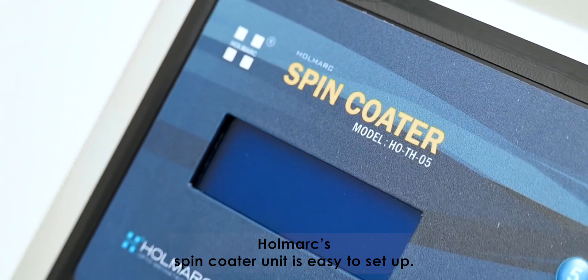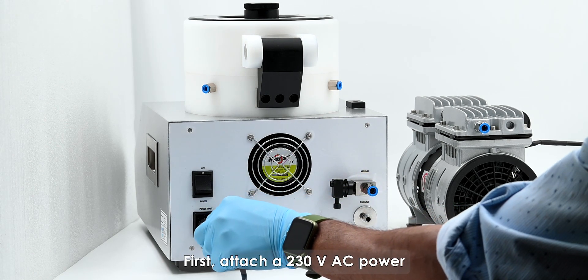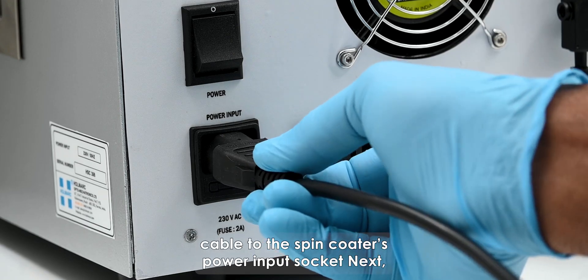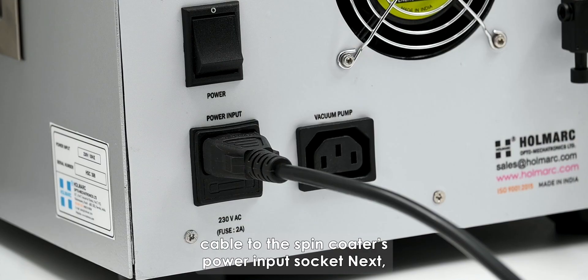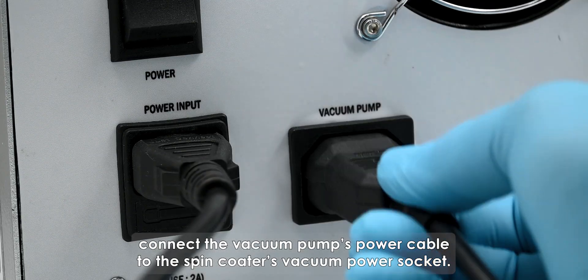Holmarc's spin coater unit is easy to set up. First, attach a 230 volt AC power cable to the spin coater's power input socket. Next, connect the vacuum pump's power cable to the spin coater's vacuum power socket.